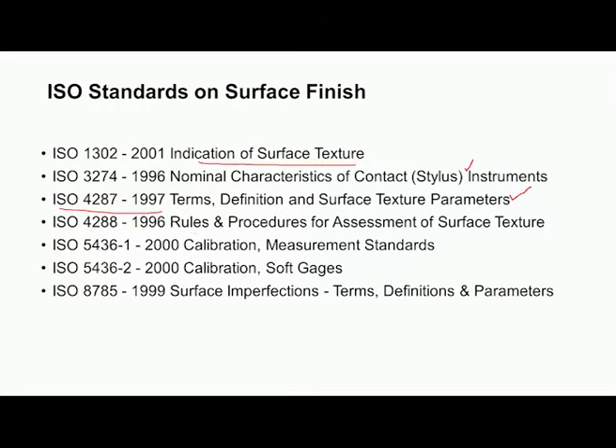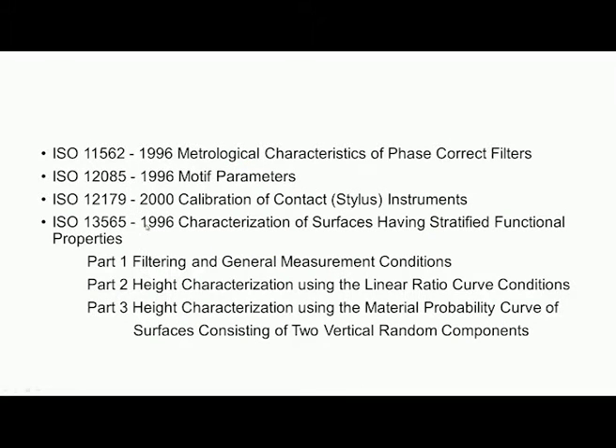And then we have standards for rules and procedures for assessment of surface texture. That means how to set up the instrument, how to set the workpiece, how to select the various parameters like cutoff length, assessment length, etc. And then how to calibrate the instruments, what are the various measurement standards that are available, and what are the various imperfections on the surface. Their definitions and parameters are also explained in these standards, and there are standards to cover the motif parameters, and standards are available regarding calibration of stylus instruments. So like this, various ISO standards are available, which will help us in assessing the surfaces.